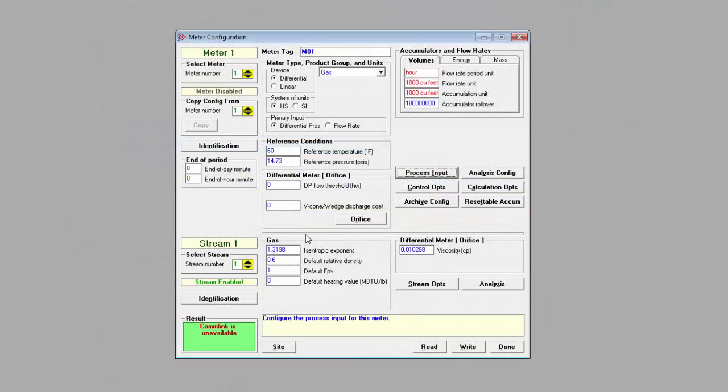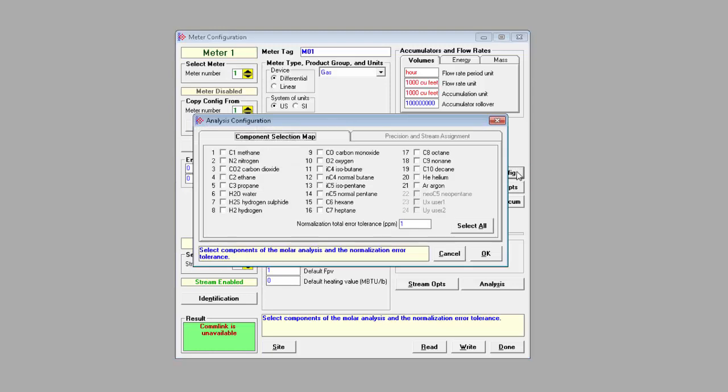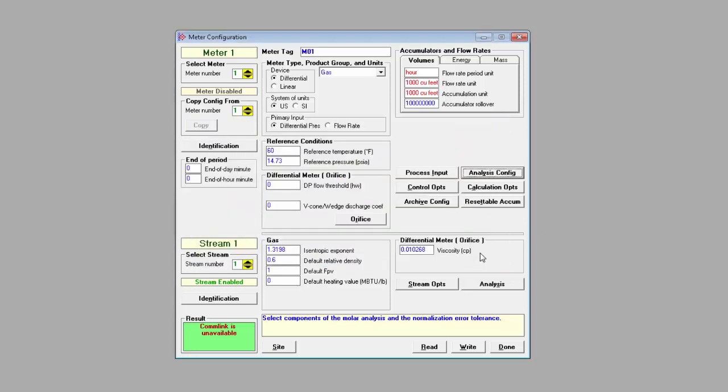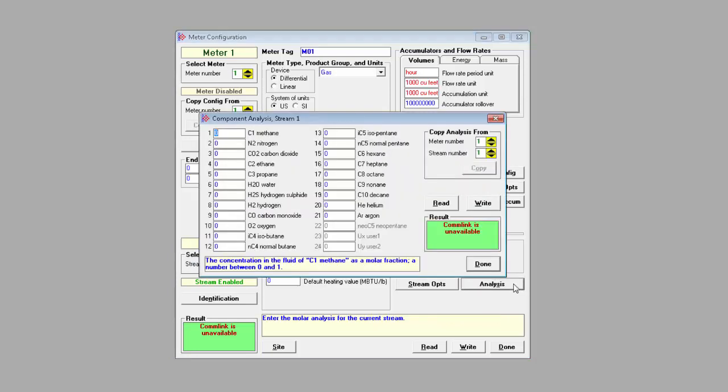If you're setting up a gas meter run, you'll need to configure the molar analysis settings. First, click the analysis config button in the meter configuration box and under the component selection tab you can select all the components to be analyzed. Now we suggest that you select all because this is what the sample add-on instruction expects. You would also need to set the normalization total error tolerance value and click OK. Next, click on the analysis button under stream 1 and here you'll set the concentration percentage for each of the components that you'll be analyzing.